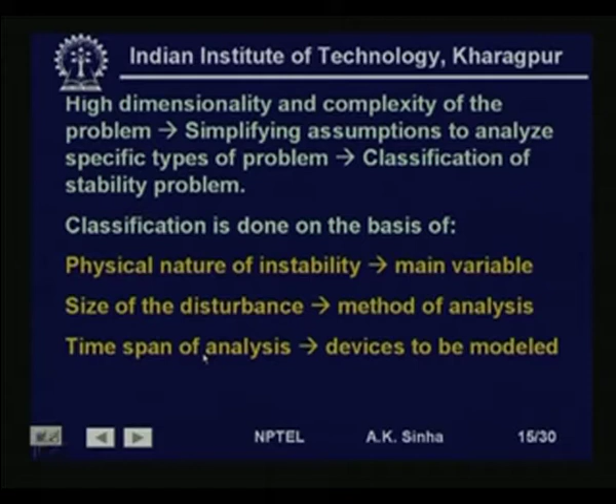So on this basis we classify the power system stability. The classification is shown here. Based on the phenomena under study, power system stability can be classified as rotor angle stability, frequency stability, and voltage stability. All these can have small signal stability, that is for small disturbances, and large signal stability or large disturbances, which we normally call the transient stability problem. And these can be done normally for short term. Normally these studies are done for a 2 to 10 second time period, whereas frequency stability is generally for large disturbances only.